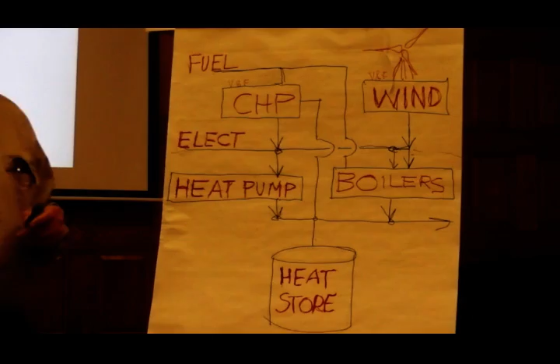But I wanted to introduce you to this problem. Now the CHPs are down and we're meeting that 20 to 25% limit. How can we move that limit out? The first way is, at least during the winter, I can connect electric boilers to the wind. Before running into the too-much-wind problem, if the CHPs are responding to an electrical call and I don't have enough heat, we can modulate the CHP downwards, but now I can't supply the heat.